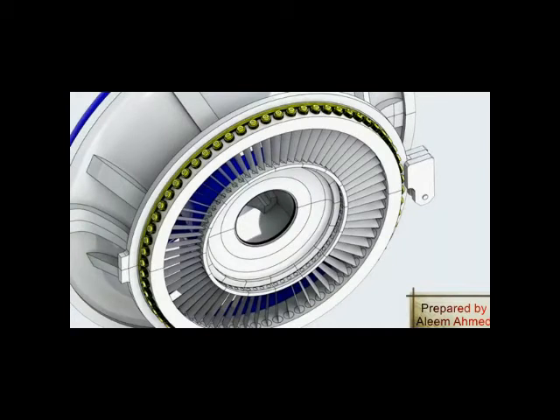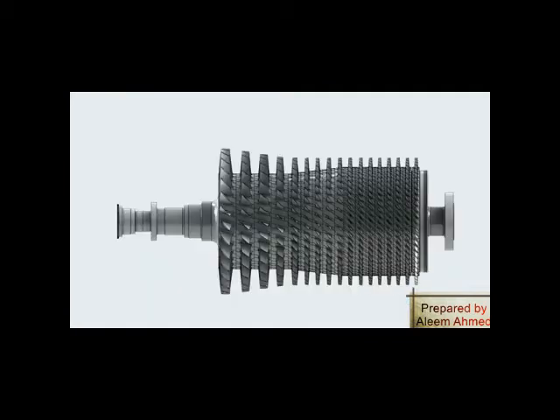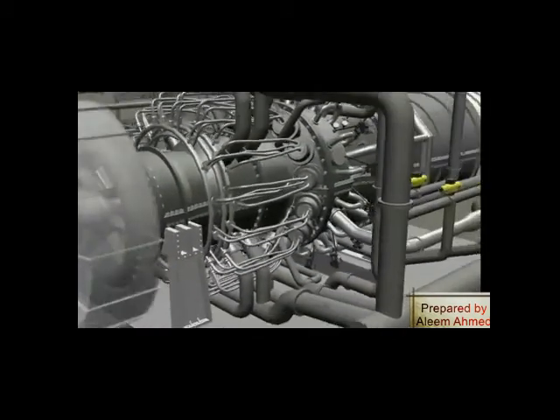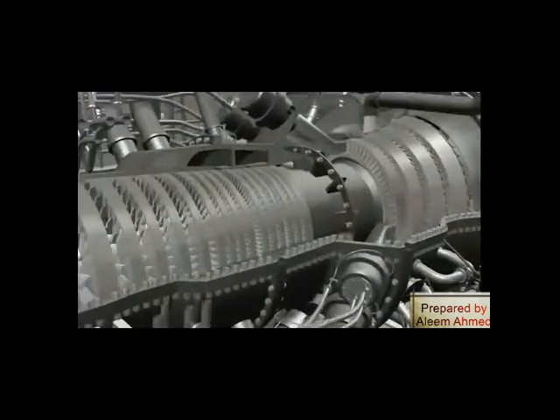The control ring is positioned by a hydraulic actuator to obtain the desired inlet guide vanes opening angle. The compressor is an eighteen-stage axial flow unit. Each set of rotating blades and stationary vanes make up a stage. The numbering is unique in that the first stage is the zero stage: R0, R1, R2 up to row 17 are the rotating blade stages. S0 to S17 are the vane stages. Including the IGVs, all vanes direct air to the next stage of blades. The rotating blades force the air into progressively smaller spaces as the air passes through the compressor.